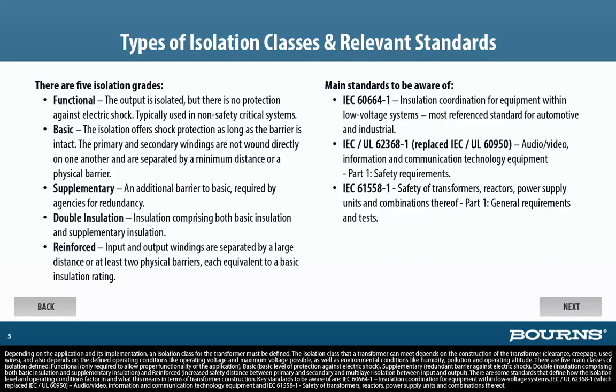There are some standards that define how the isolation level and operating conditions factor in and what this means in terms of transformer construction. Key standards to be aware of are IEC 60664-1, Insulation Coordination for Equipment within Low Voltage Systems, IEC/UL 62368-1, which replaced IEC/UL 60950, Audio Video Information and Communication Technology Equipment, and IEC 61558-1, Safety of Transformers, Reactors, Power Supply Units, and Combinations thereof.